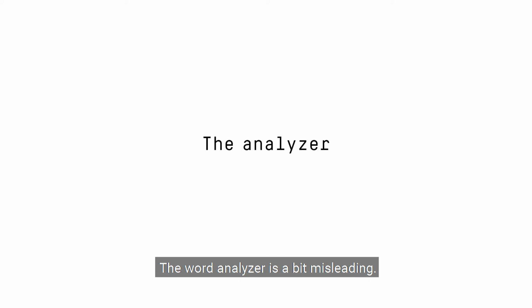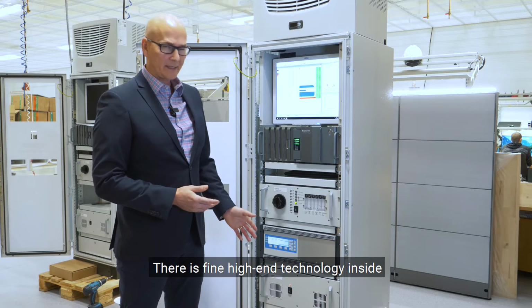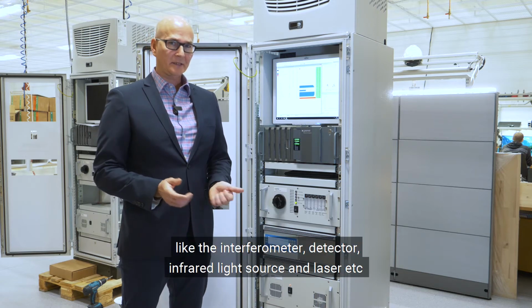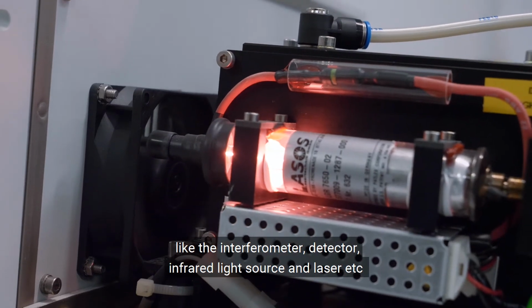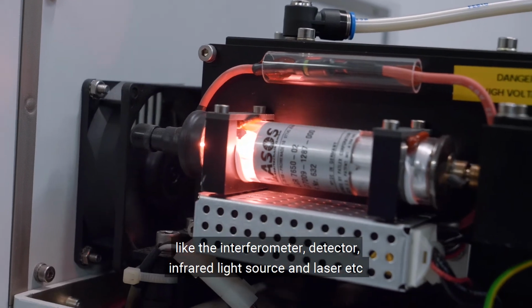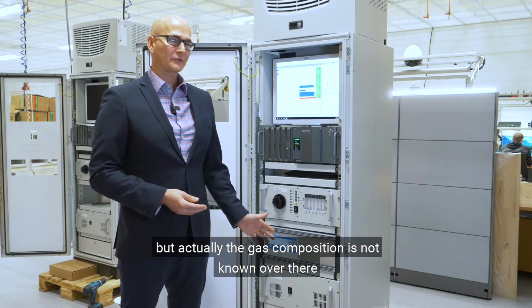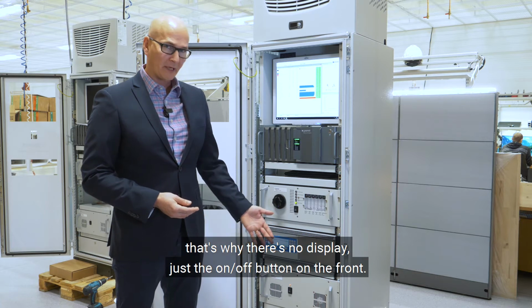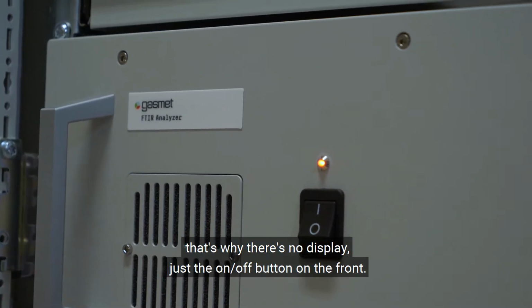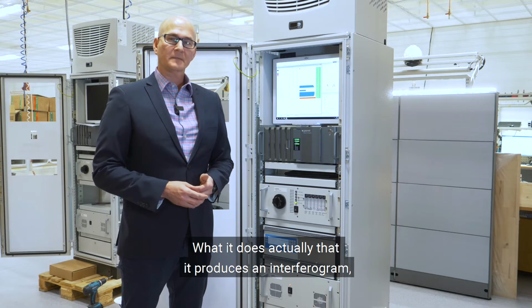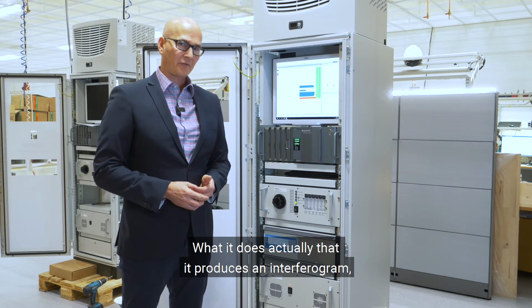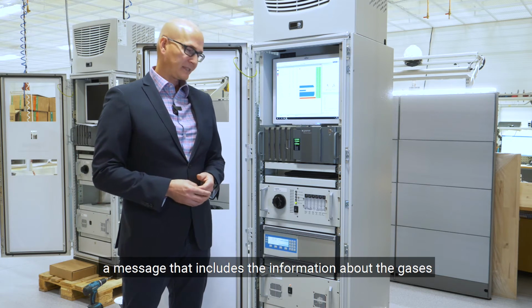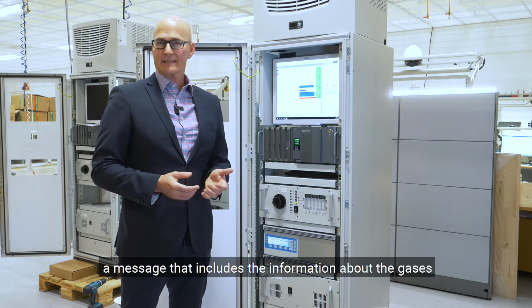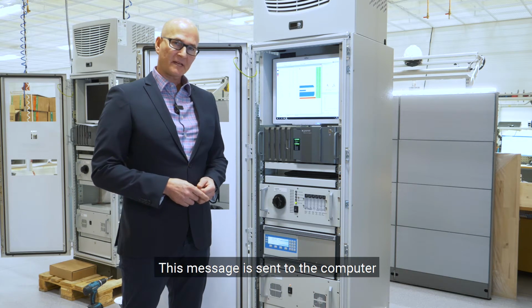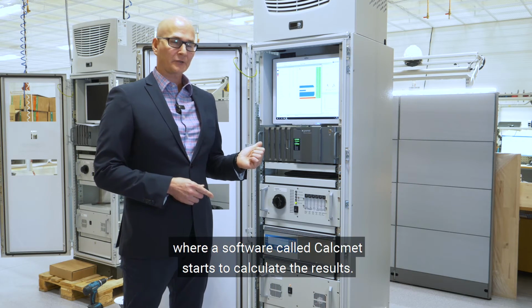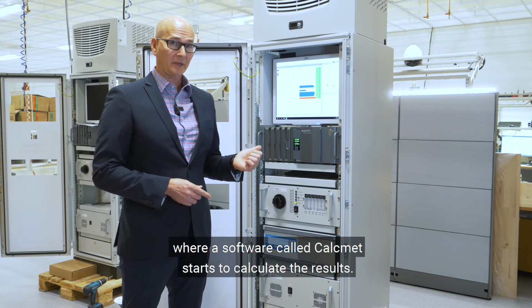The word analyzer is a bit misleading. There is fine, high-end technology inside, like the interferometer, detector, infrared light source and laser, etc. But actually, the gas composition is not known over there. That's why there's no display, just the on-off button on the front. What it does is that it produces an interferogram, a message that includes the information about the gases which are present in the sample gas. This message is sent to the computer, where a software called Calcmet starts to calculate the results.